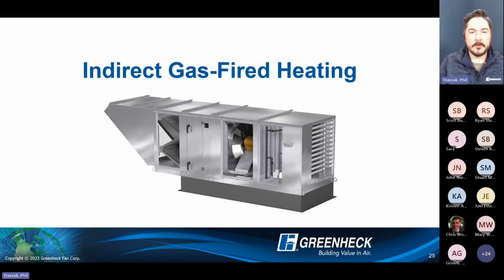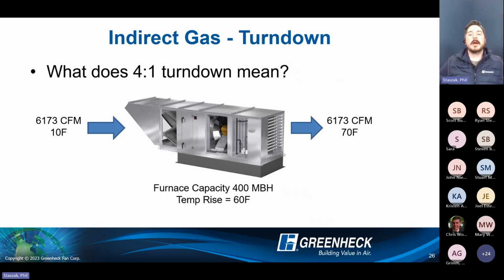All right, so now let's shift toward indirect gas fired. I mentioned the turn down capacity. Well, what exactly does 4-to-1 mean? Now remember, direct gas fired has 25-to-1 built in, but the math is going to be the same here. So when we're talking about what 4-to-1 turn down actually is, you design a system around 6,173 CFM. You want to discharge 70 degrees on a worst design day where it's 10 degrees outside. Furnace capacity, 400 MBH required to get you that temp rise of 60 degrees. That's a typical design. Now for the 4-to-1, you take your temp rise and divide it by that first number. So 60 divided by 4 gets you your minimum.